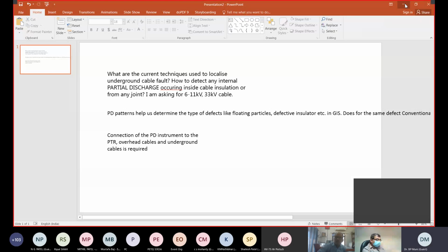If nothing is specified, and if it's polyethylene, then you can't do anything - you have to replace that part if you can pinpoint it. In a transformer, I'm not an expert, but it depends on exactly where inside the transformer, if it's possible. In some cases, with acoustic combined with electrical measurements, you can pinpoint it within half a meter, and if you know the design of the transformer, you can tell where it's dangerous.